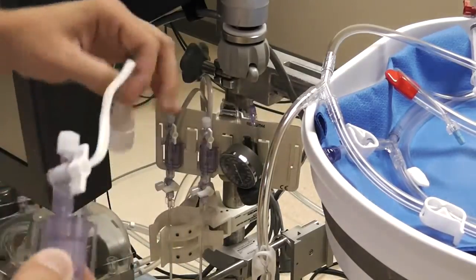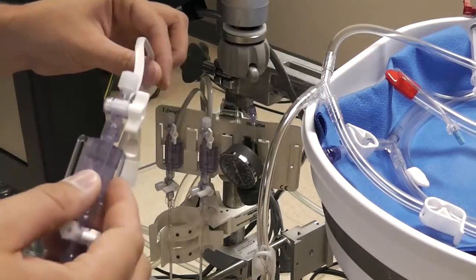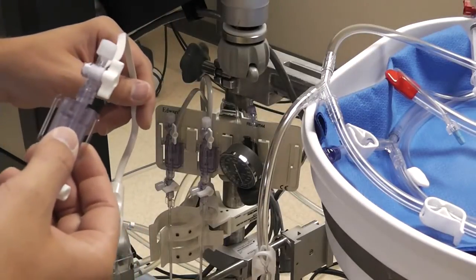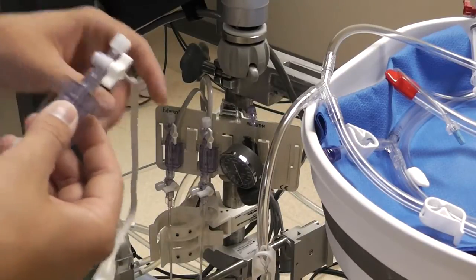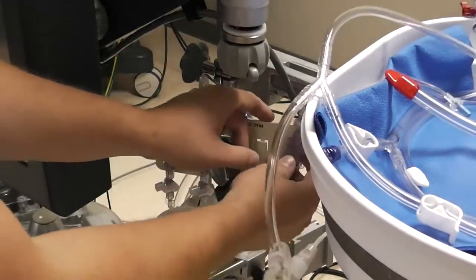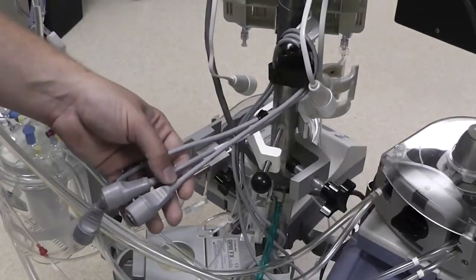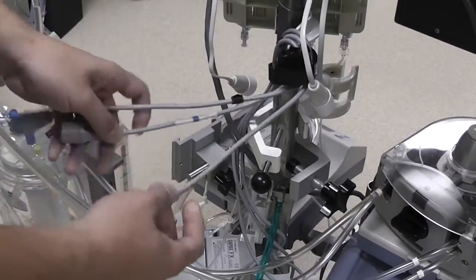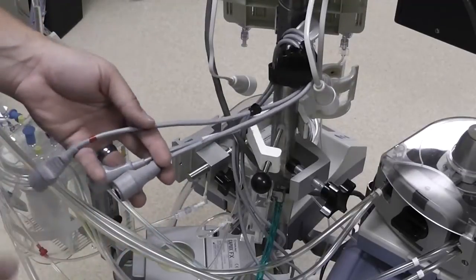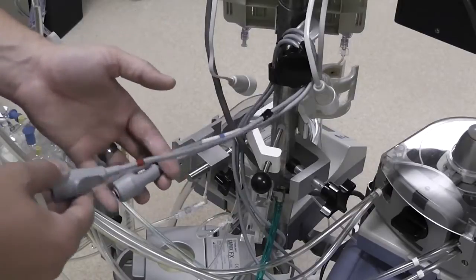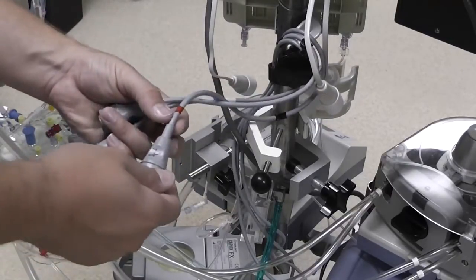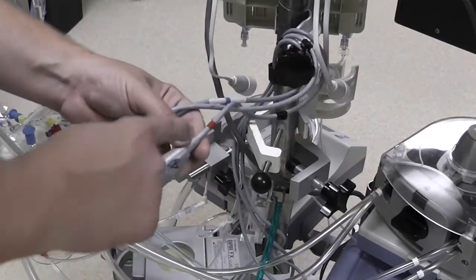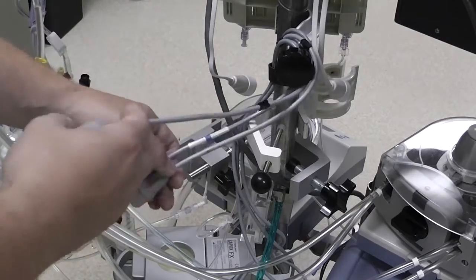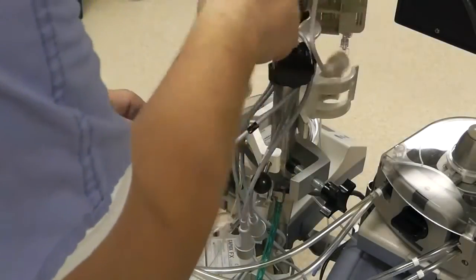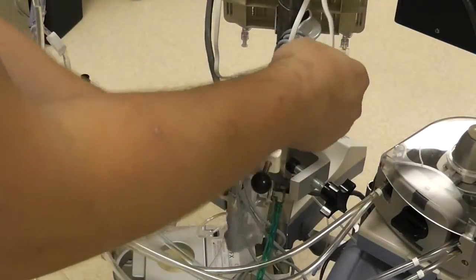The last one is the retrograde one, which has no line pre-attached to it. That will get attached to the retrograde line in the OR. So, that's going to go to the far right. So here we have the 3 pressure transducer lines, and you'll notice these are all labeled differently on the different machines, but the arterial one will always either say ART or have an A on it like that, or be marked red, something similar to that. So that one is going to go to the arterial transducer.